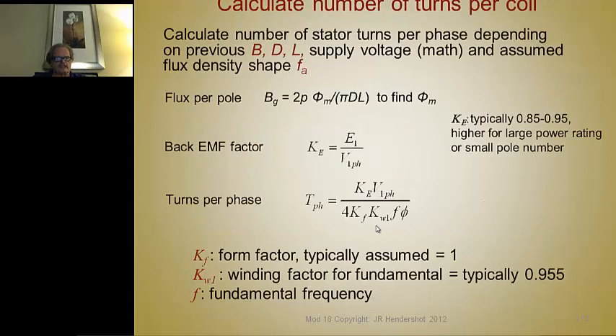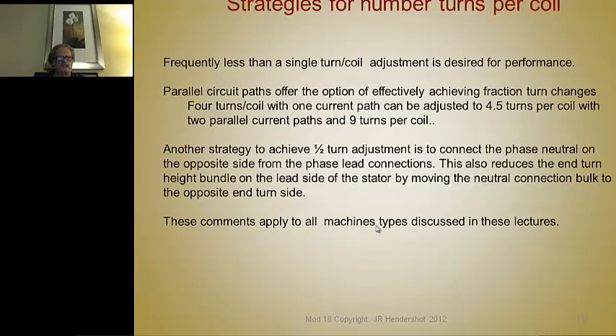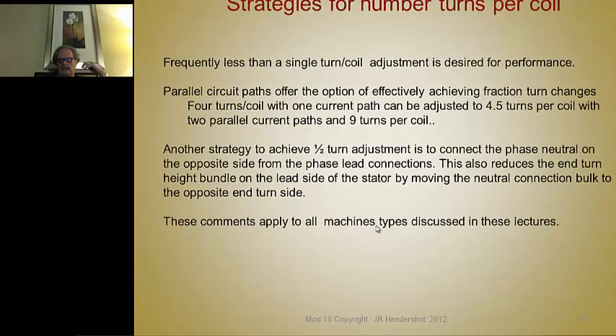Here's the formula to calculate the flux per pole — from that you calculate the turns per coil. There's sometimes difficulty in picking the right number of turns, so here are some strategies. Sometimes less than a single turn per coil is required, so parallel circuit paths can be effectively used. For example, if you've calculated you need four and a half turns per coil, but you can only put in four or five if all the coils are in series, using two parallel paths with nine turns per coil is effectively like four and a half turns.